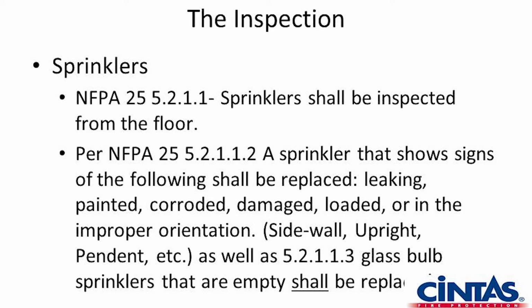Painted sprinklers: there are two things that paint causes an issue with. If the paint is on the deflector where the little slits are, those slits are very specific in the design of that sprinkler, and they control where the droplets from the head go. In a residential situation, we'll have a sprinkler head with very tight, very small gaps around that circular deflector. That tells us we're going to get a very light spray of water across the area the sprinkler head is protecting. If you look in a more hazardous area, like warehouse storage, there will be very large gaps on the circular deflector, indicating that the water, once it hits that deflector, is going to be dispersed with larger droplets.